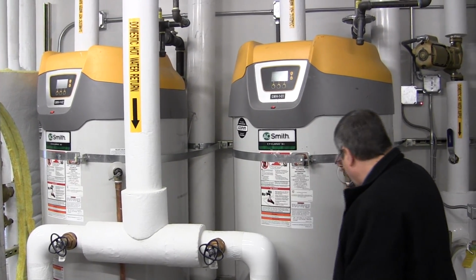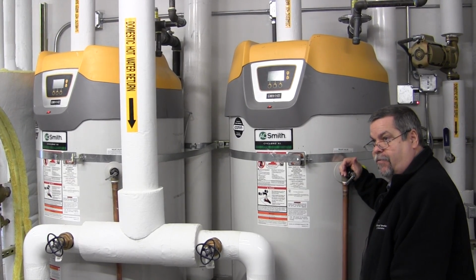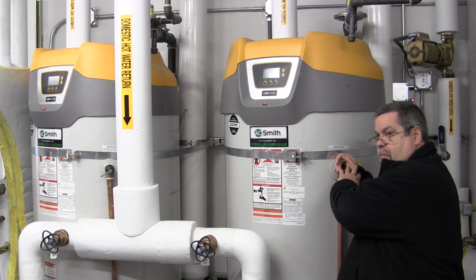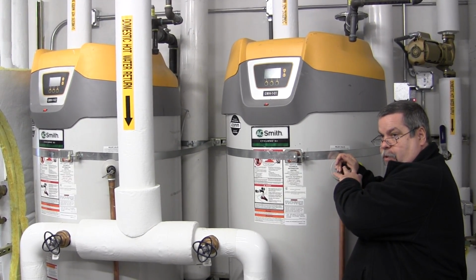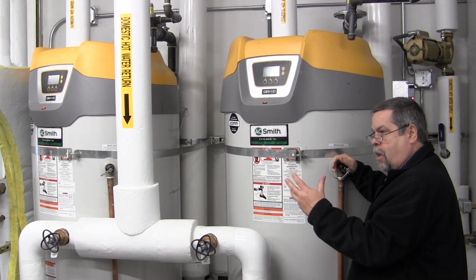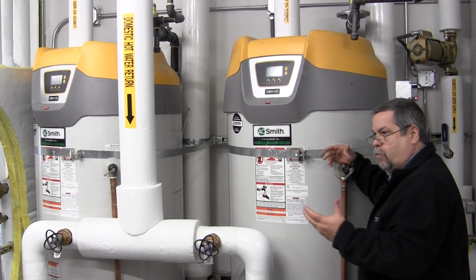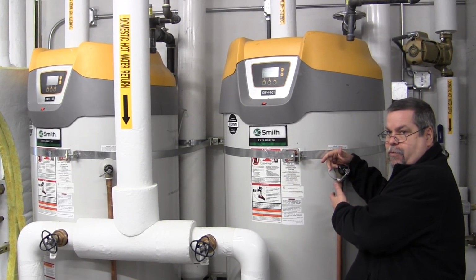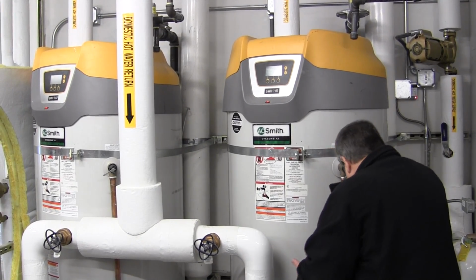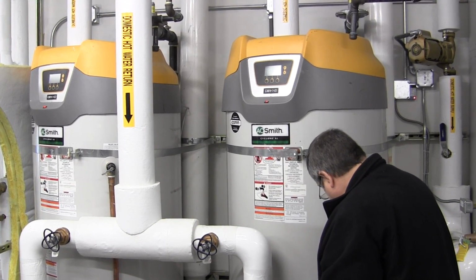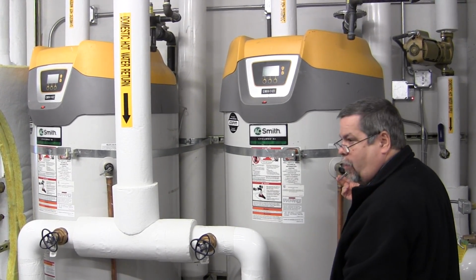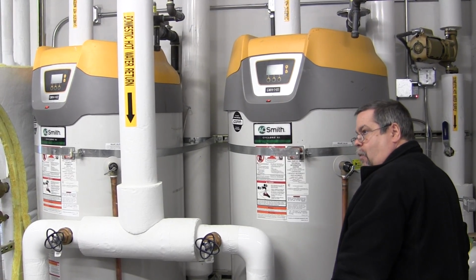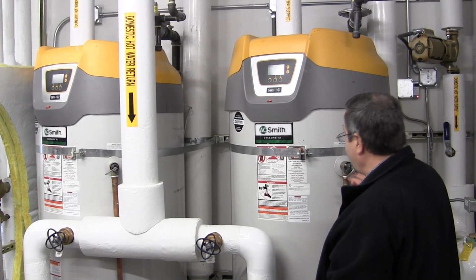This is your temperature and pressure relief valve. It is the main safety device on this unit that protects you if anything should go terribly wrong and the controls weren't to work. This would prevent energy from being stored and causing any issue. If you pull this, it lets the hot water go down there. You can check that annually.